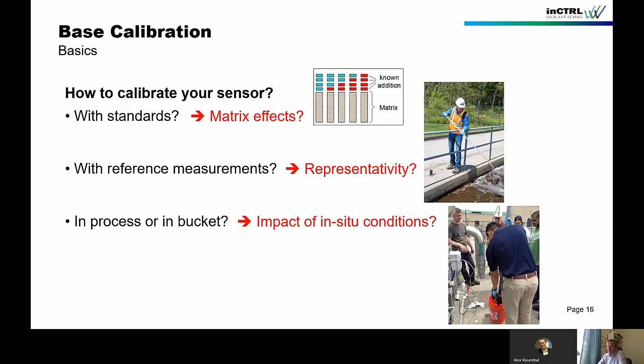If you want to work on that problem of being representative, you may go for what we call a bucket experiment. This is basically for in situ sensors, where you put the probe into a well-mixed bucket, and then you sample out of that bucket and analyze that in the lab. However, some of these in situ probes are quite sensitive to the in situ conditions, so it might not be a good idea because then they show different results. Unfortunately, you have to do that sensor by sensor and also location specific, so that is really something where you have to put that into a maintenance plan.